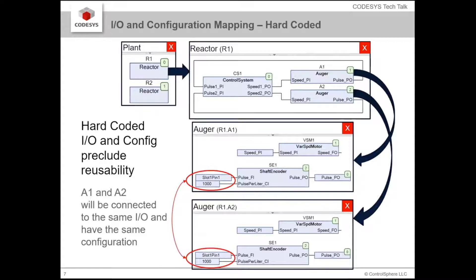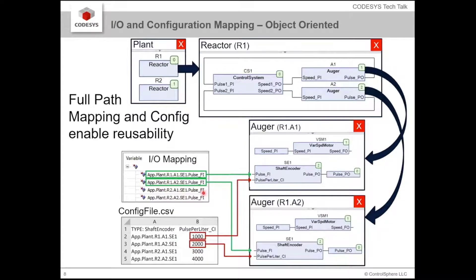So how do we fix that? CodeSys has a really great technique for handling the IO — it was genius the way they came up with this. Instead of mapping your IO to a global variable like we always have in the past, you map it using a full path name. So here we have the plant, the R1 reactor, the A1 auger, and the SE1 shaft encoder. We map this to app.plant.r1.a1.se1.pulsefi — that input. That IO point has been mapped to that instance. We do the same for A2, and for the second reactor R2. Now the centralized IO points are mapped out to all these distributed objects.